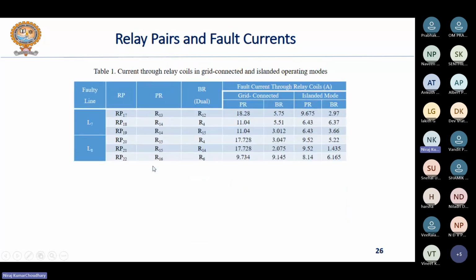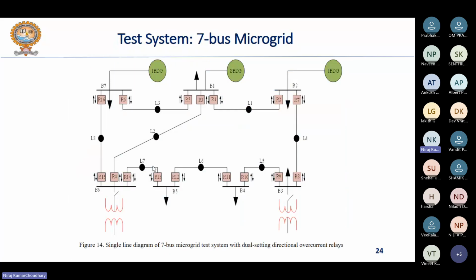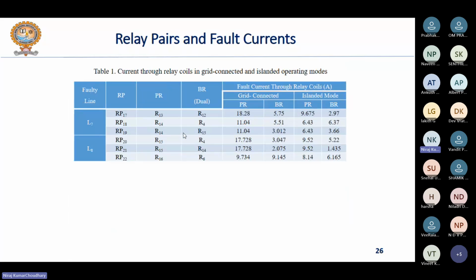So there are 8 fault locations we have considered, means there are 8 lines in this 7 bus microgrid system from L1 to L8. So accordingly, we have formulated the different 22 relay pairs, right? For every relay pair, there are primary relay as well as backup relay.